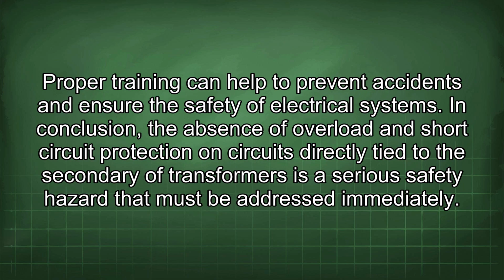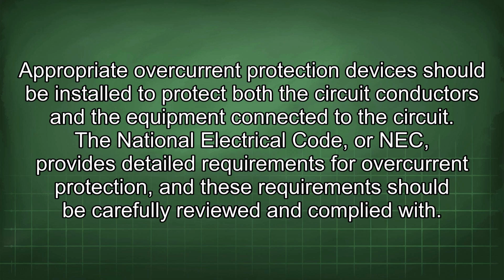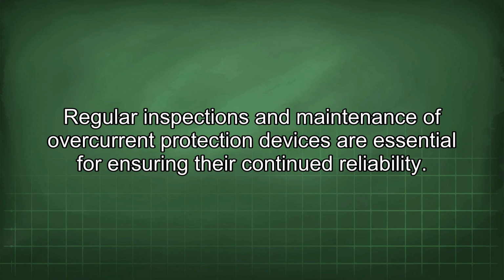In conclusion, the absence of overload and short-circuit protection on circuits directly tied to the secondary of transformers is a serious safety hazard that must be addressed immediately. Appropriate overcurrent protection devices should be installed to protect both the circuit conductors and the equipment connected to the circuit. The National Electrical Code, or NEC, provides detailed requirements for overcurrent protection, and these requirements should be carefully reviewed and complied with. Regular inspections and maintenance of overcurrent protection devices are essential for ensuring their continued reliability.